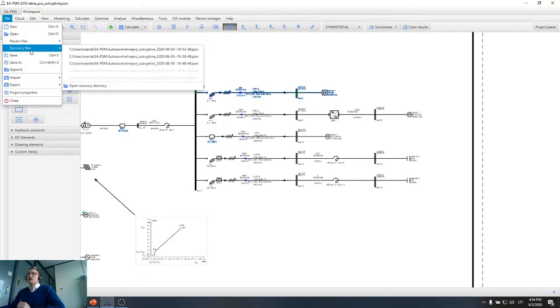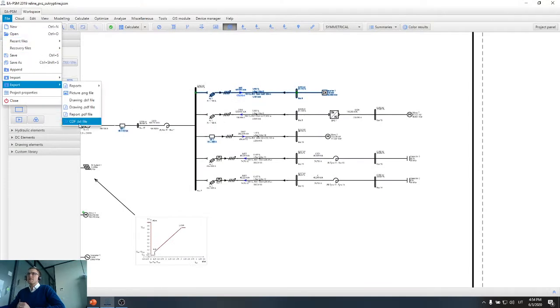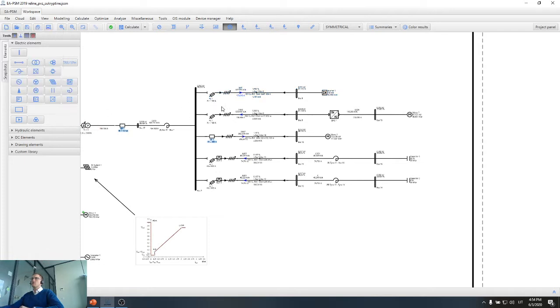There was a question about whether it is possible to import data into the software from other software. Basically you can import using the CDF format, an industry standard format, to import from one software to another. So in PSCC you can export CDF and then import into our software. The problem with the format is that it does not include any information about the protection coordination devices. So you will still have to add the protection coordination devices manually. But for example, PCC software does not have protection coordination like we have in our software, so it's not a huge problem. If you want to import from PCC, you can use the CDF format and then add the protections manually here with our software.